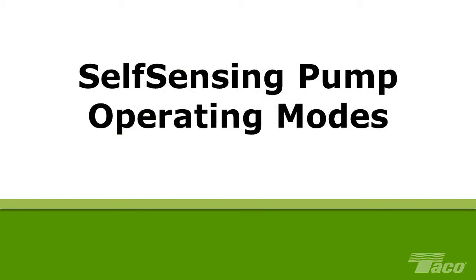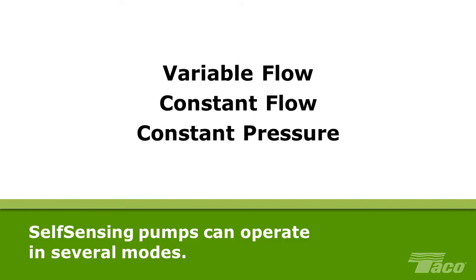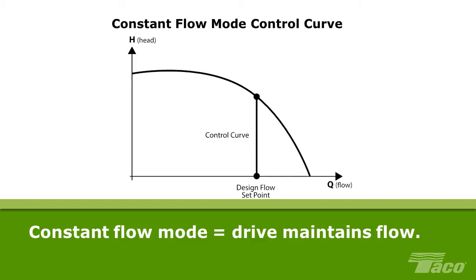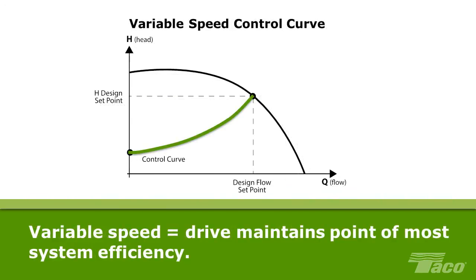Self-Sensing Pump Operating Modes. The Taco self-sensing pump can operate in one of several modes based on the shape of the control curve. In constant flow mode, the drive maintains the desired flow regardless of system resistance — indicated by a vertical control curve. In constant pressure mode, the horizontal control curve indicates the drive maintains the same pressure regardless of system resistance. In variable flow and head applications, the control curve represents the theoretically most efficient system operation throughout the pump's operating range, based on the best placement of a differential pressure sensor. For more information, please see the video on control curves and setting self-sensing pump control modes.